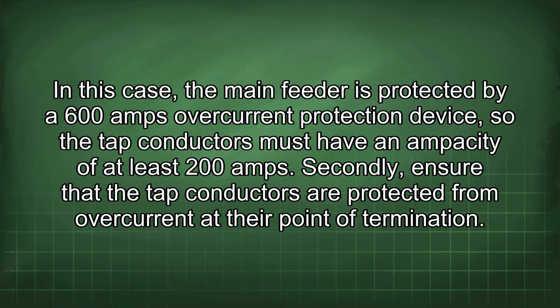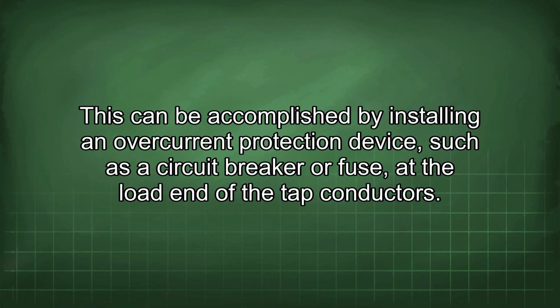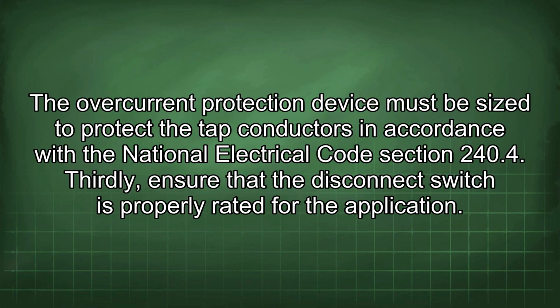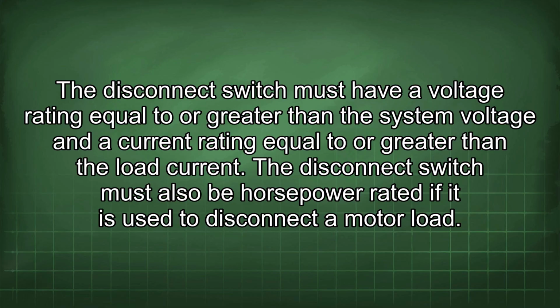Secondly, ensure that the tap conductors are protected from overcurrent at their point of termination. This can be accomplished by installing an overcurrent protection device, such as a circuit breaker or fuse, at the load end of the tap conductors. The overcurrent protection device must be sized to protect the tap conductors in accordance with the National Electrical Code Section 240.4. Thirdly, ensure that the disconnect switch is properly rated for the application. The disconnect switch must have a voltage rating equal to or greater than the system voltage and a current rating equal to or greater than the load current. The disconnect switch must also be horsepower rated if it is used to disconnect a motor load.